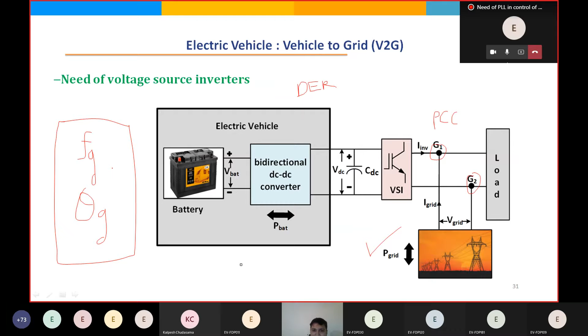So if you want to connect this inverter to the grid, the frequency of the inverter should be the same as the grid frequency. The phase angle of the voltages should be the same as the grid voltages. The amplitude should be the same. That means I can control my inverter as per this requirement only if I have data from the grid. I need the grid frequency Fg and the phase angle theta g. So these things are required, right? My synchronization requires a PLL, whose role is to determine this data.